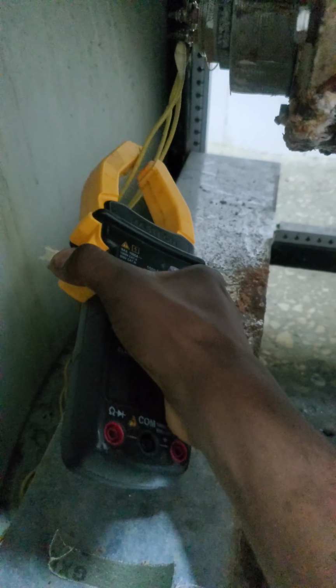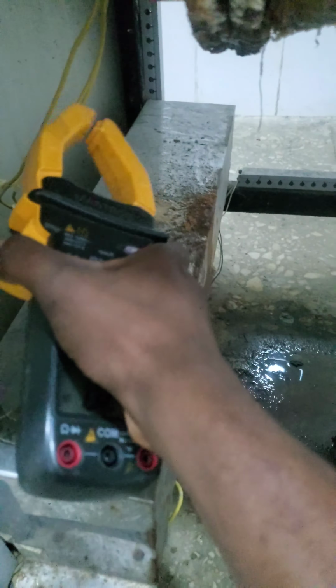By the way, those cables are connected to a 3-phase heater. The heater is connected using a delta connection, so that's why you see only 3 cables. If it is a star connection, it will be 4 cables, with the last one being the neutral, but here there is no neutral.